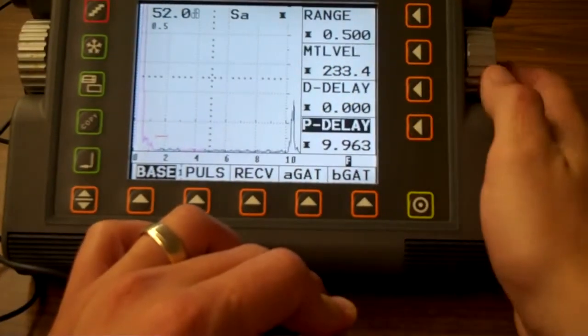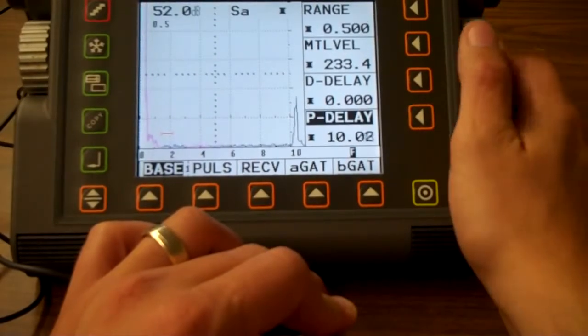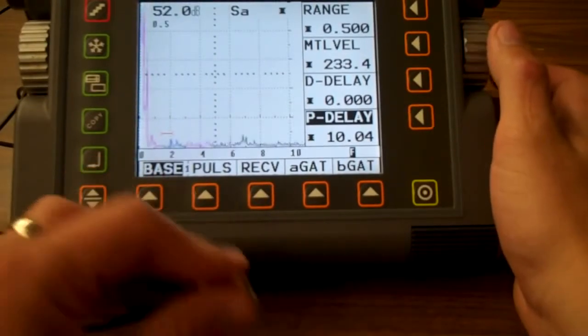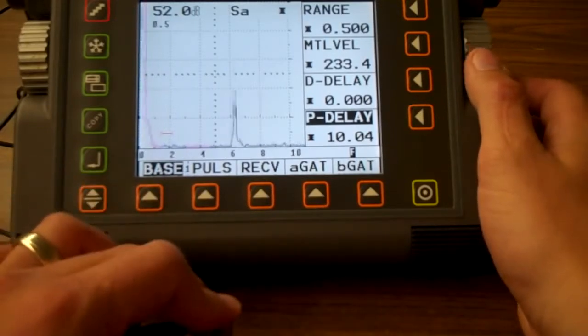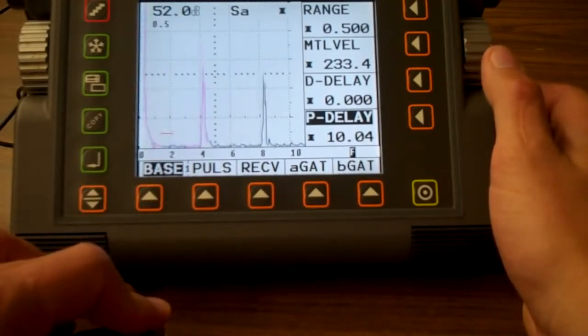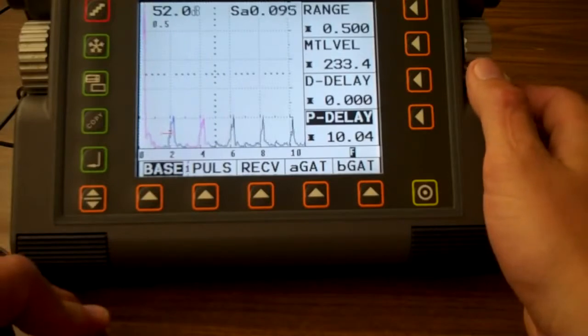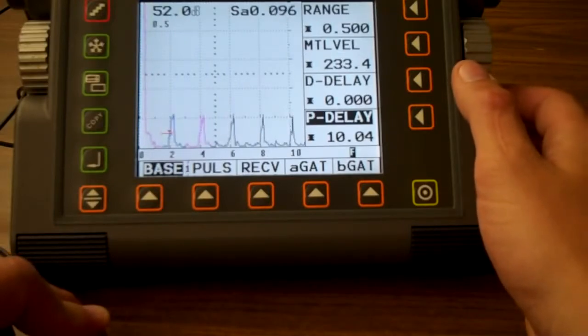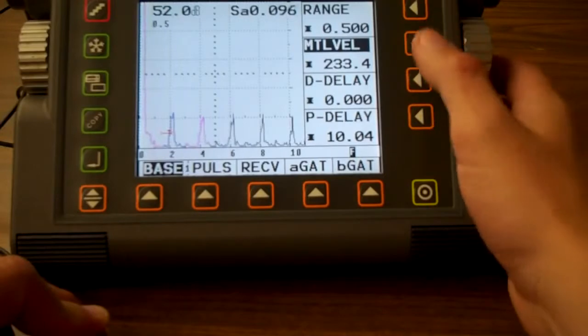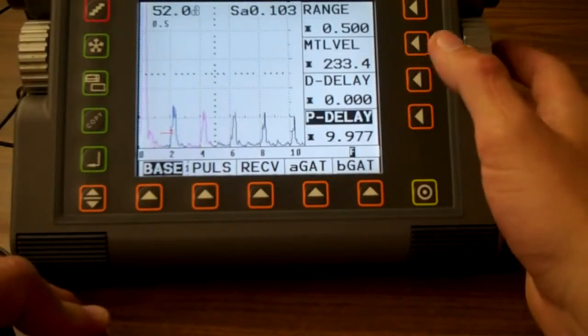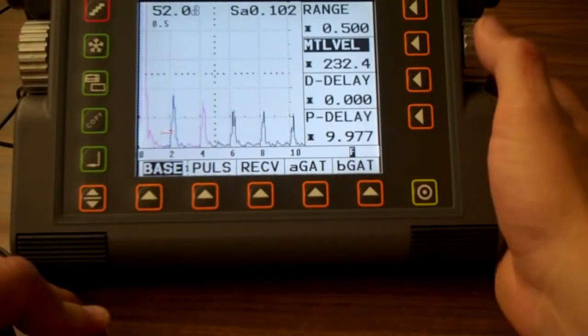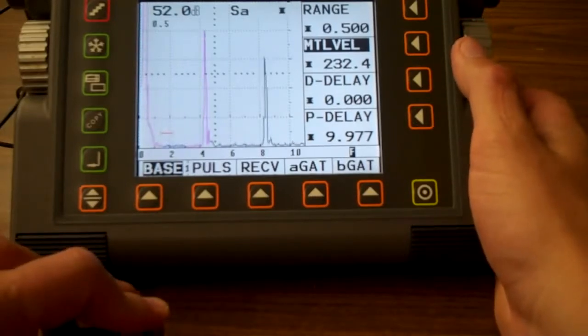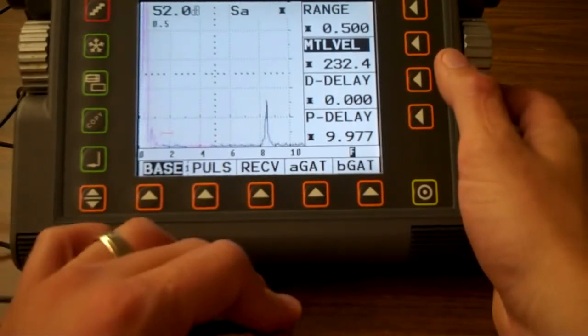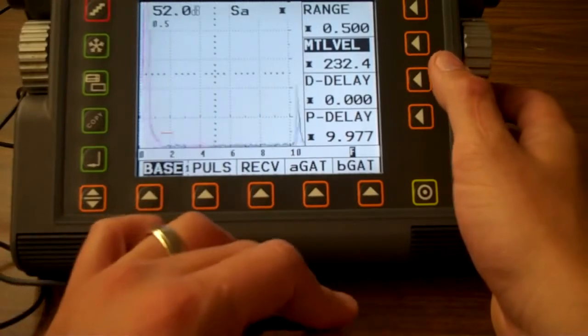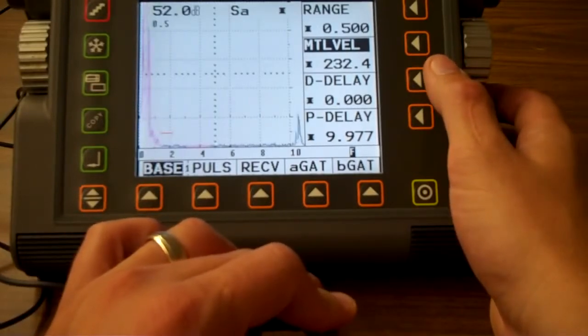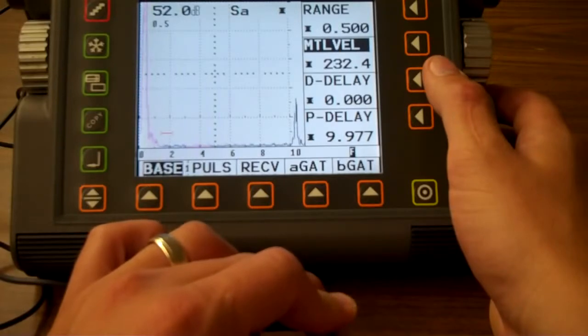I'm going to go back down here to my probe delay and push that over just a little bit. There we go. Right on 80%, right on 60%, right on 40 and 80. And there's my 20, 40, 60, 80. Got a little issue there. I'm going to probe delay this guy back, and then I'm going to velocity him in. So this is where you fight it for the longest time. Right on 60, right on 80, and there we are. Basically right on 100, just barely past.